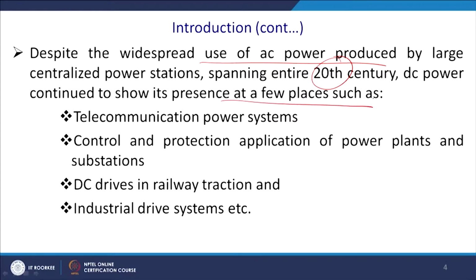Communication towers require DC power, as do control and protection applications in power plants and substations. If you go to any power plant, you will find a huge battery bank used to start the alternator, since the field current must come from that storage element to start generation. For this reason, you require backup power, and that backup excitation current comes from DC.